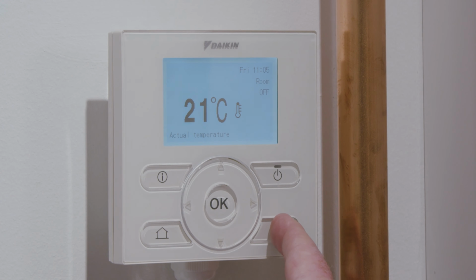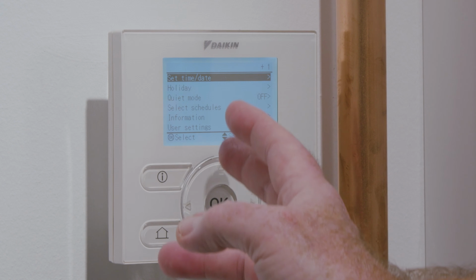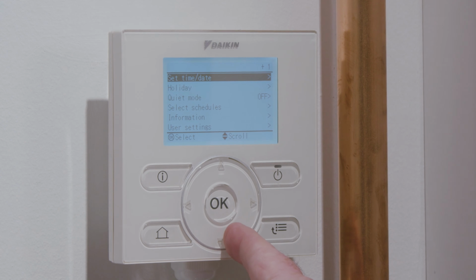But all those parameters are within the controller, and you can still change them. It's not the end of the game. Again, during the training course, you'll get detailed guidance on how to change those parameters. The key thing is, once you've populated the Quick Start Wizard, you're ready to de-aerate your heating system and your hot water cylinder. If you've got stored hot water, then there is a de-aeration program built into the controller. So you're at a point where you can start and run that de-aeration program.